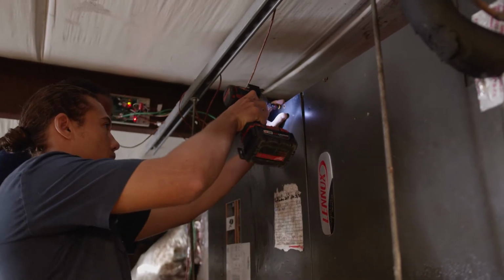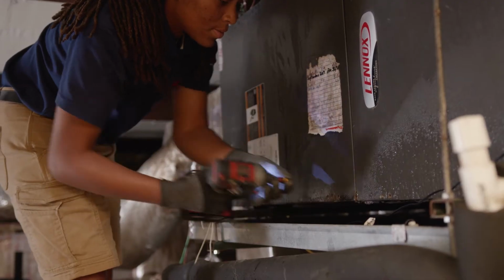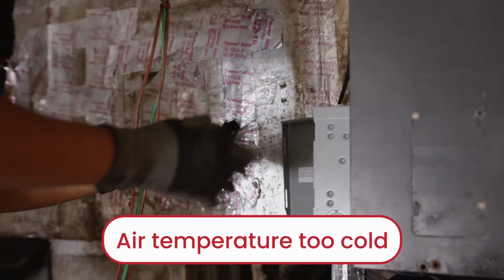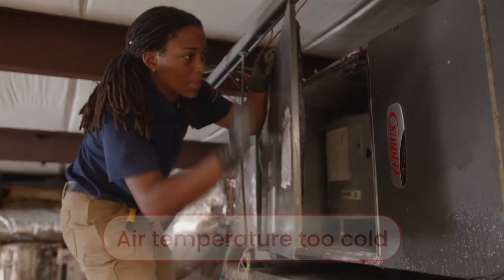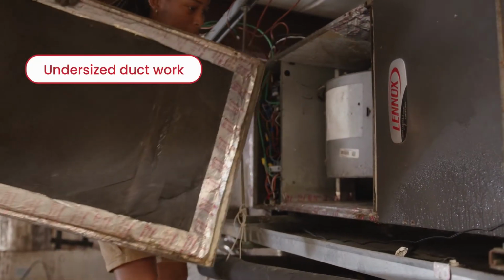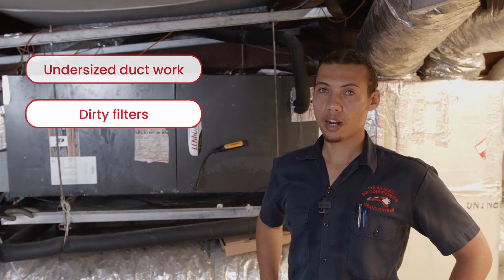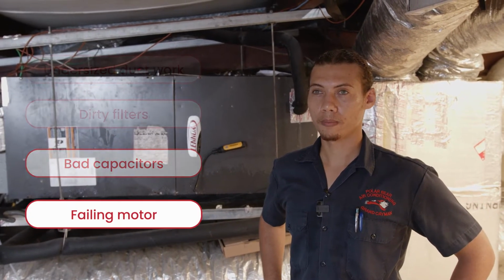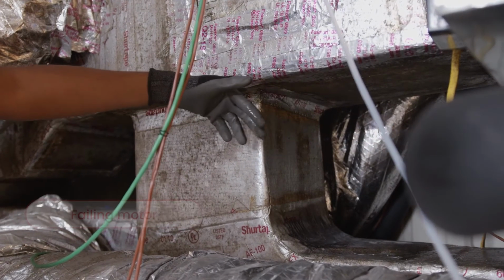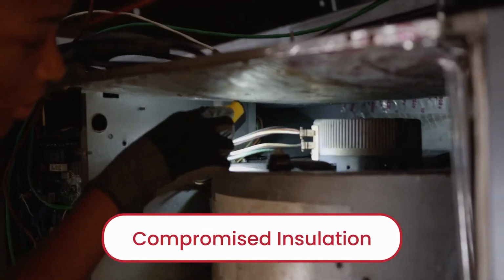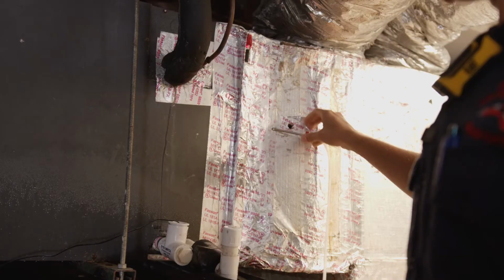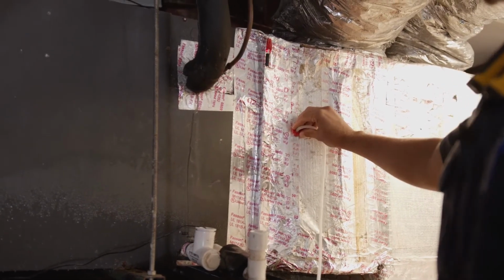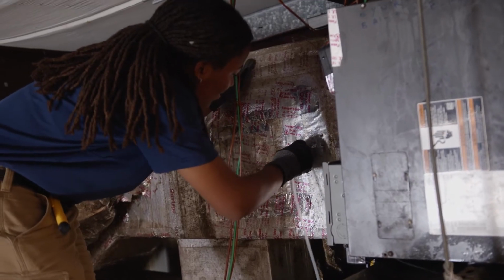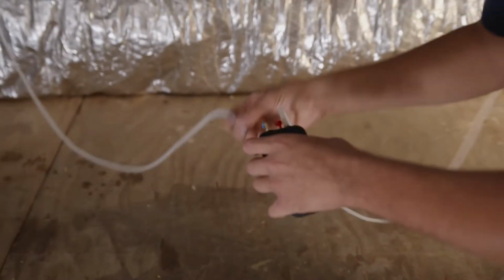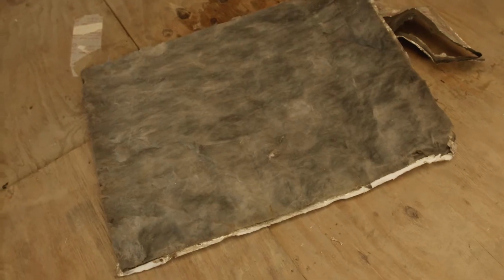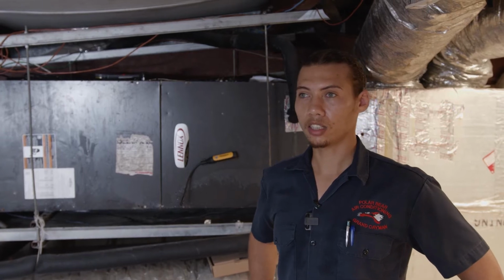Some of the causes of air handlers condensating are the air temperature being too cold. So this is caused by undersized ductwork, dirty filters, a bad capacitor, a failing motor. It can also occur due to the insulation being wet. So this is due to the high pressure in the duct distribution system caused by undersized ductwork, dirty filters, a cracked internal drain pan, the insulation becoming deteriorated or loose. And this just happens with age.